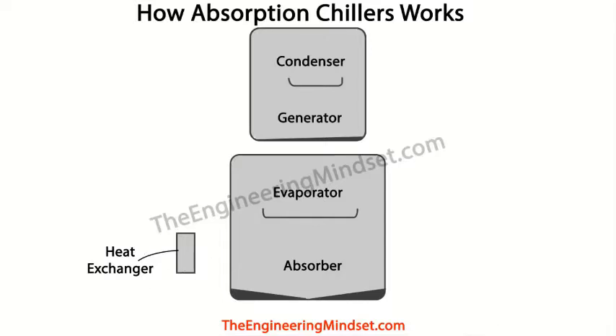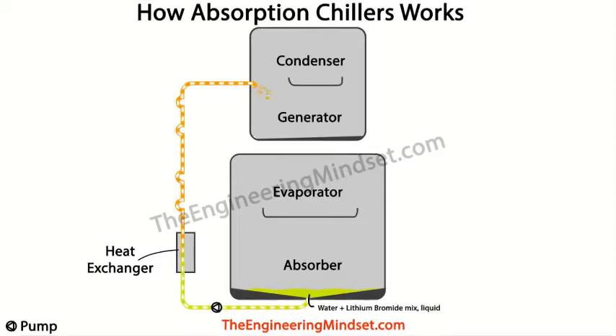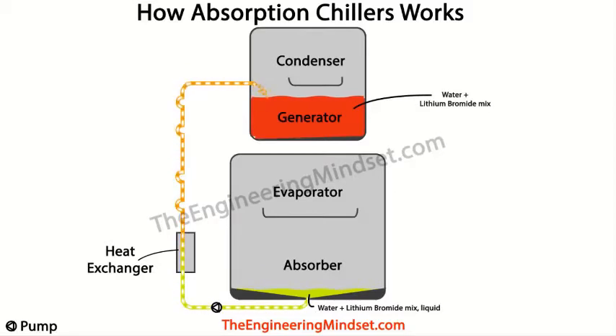The heat exchanger is just there to improve the efficiency of the system. So first of all, a mixture of around 60% lithium bromide and 40% water is pumped from the absorber through the heat exchanger and then rises up and pours into the generator tank at the top of the chiller. Now this line is often referred to as the weak solution line, and that is because the lithium bromide is mixed with the water, so it's a weak solution. The generator then fills up with this mixture of lithium bromide and water, creating a reservoir.